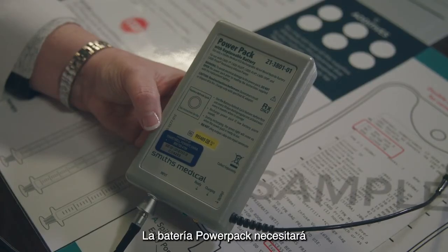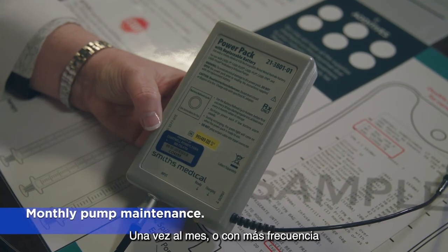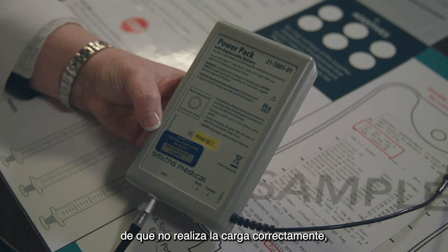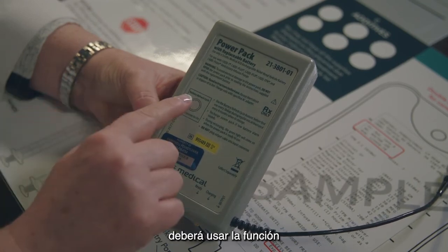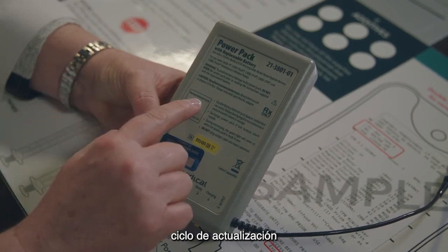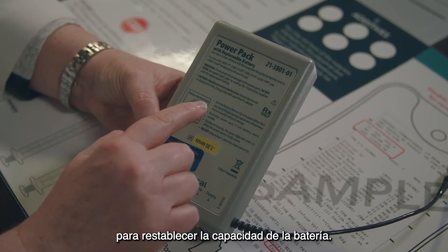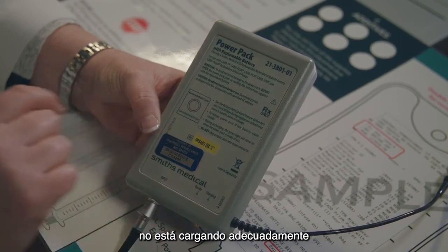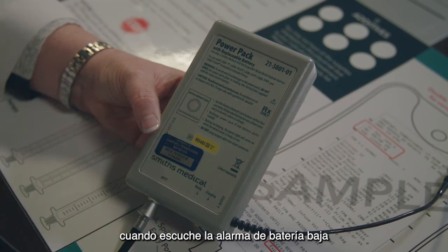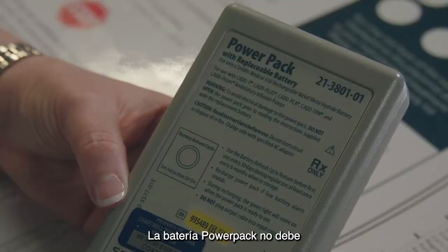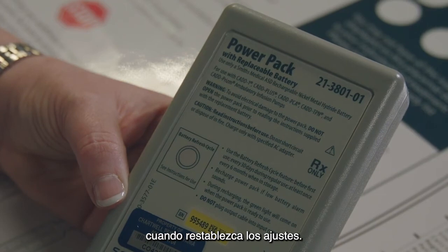Your power pack will require monthly maintenance, once a month or more frequently. If your power pack is showing signs of not holding a charge, you'll need to use the battery refresh cycle to restore battery capacity. You will know your power pack is not holding a charge when you have more frequent low battery alarms on your pump. The power pack should not be attached to the pump when you refresh your power pack.